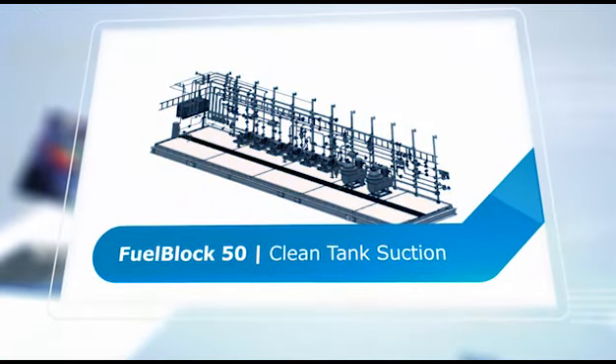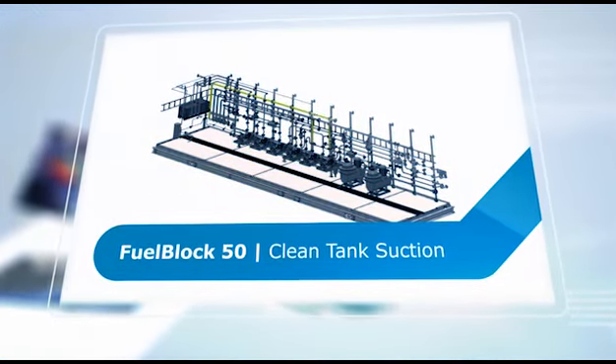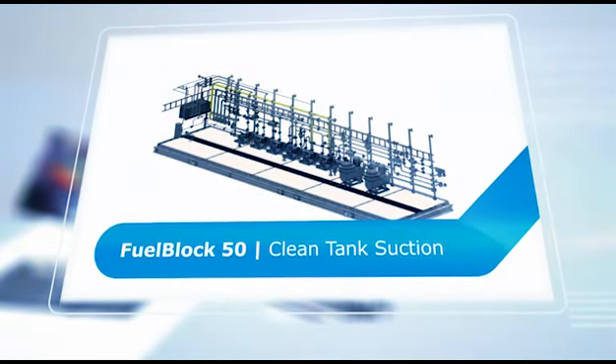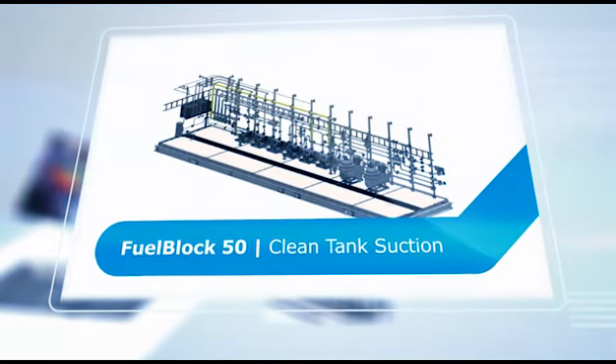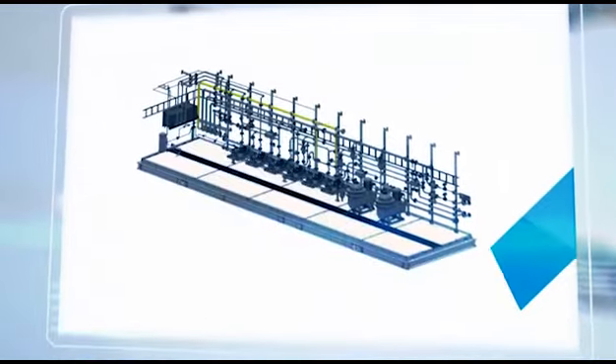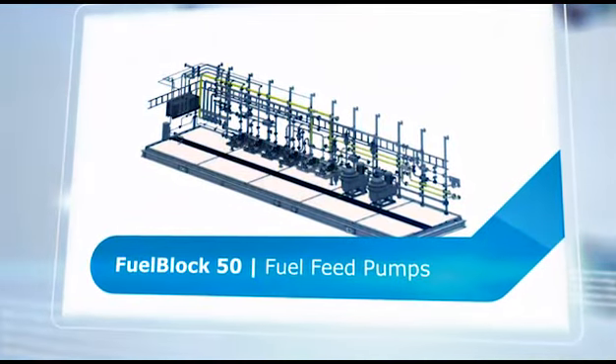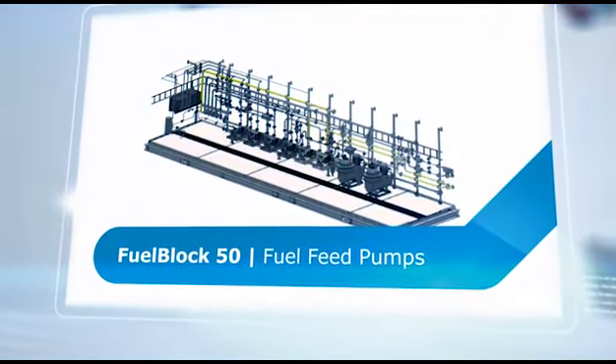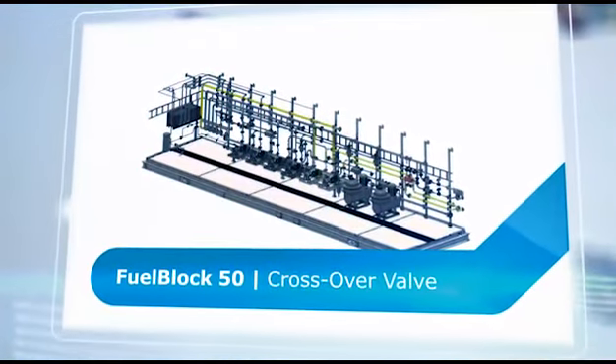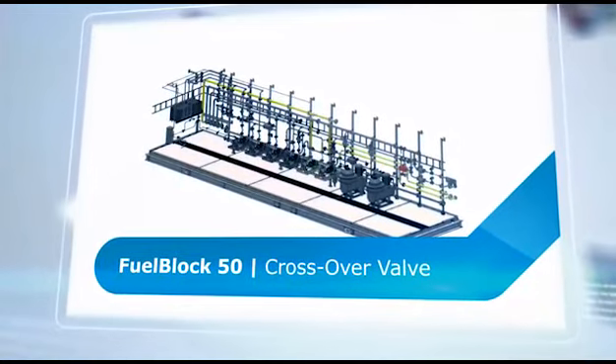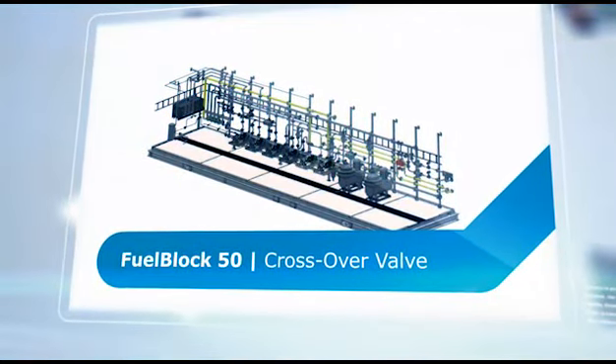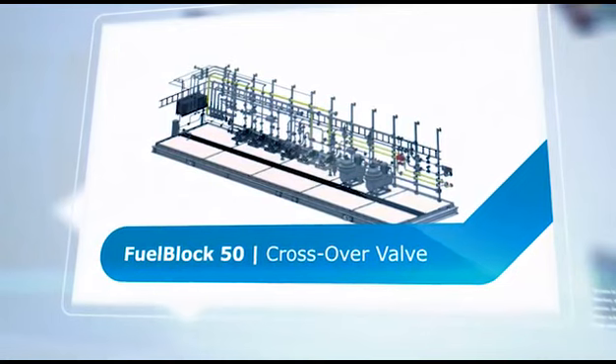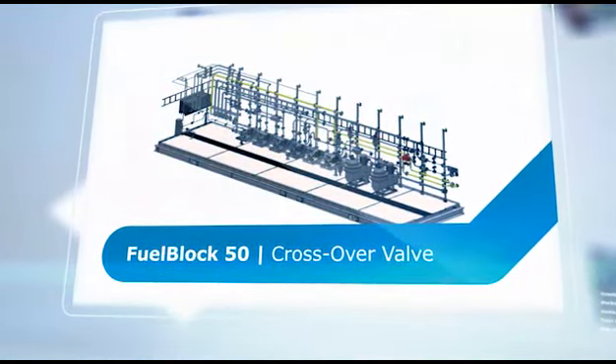The clean tank suction header is connected to either one or two clean fuel tanks. The tanks have a floating suction arrangement. The fuel feed pumps draw from the clean tanks, with each pump typically servicing a dedicated turbine. If a fuel feed pump should fail during normal operation, the other pump will start if not already running, and the crossover valve will open to maintain fuel supply to both turbines.